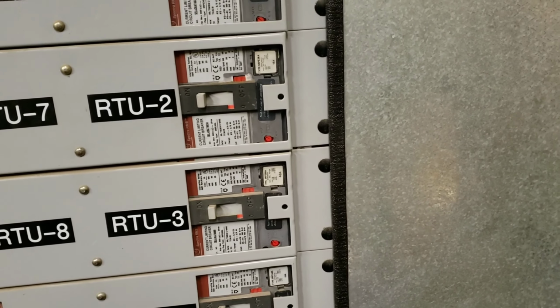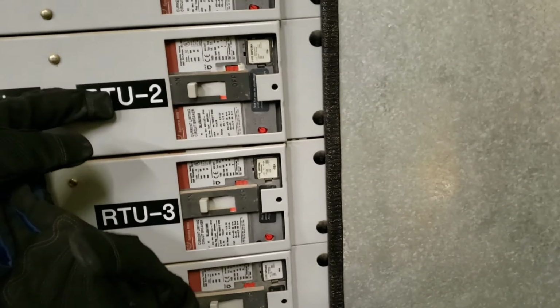Alright, so I came downstairs. The breaker we're messing with is on RTU number 2. The breaker was tripped. I turned it off all the way, then turned it back on to reset it. It was tripped, so we're gonna have to go out and figure out why it actually tripped. We're gonna test some stuff to ground to make sure we don't have a direct short. Once we figure that out, maybe we'll kick it on and see where we go from there.